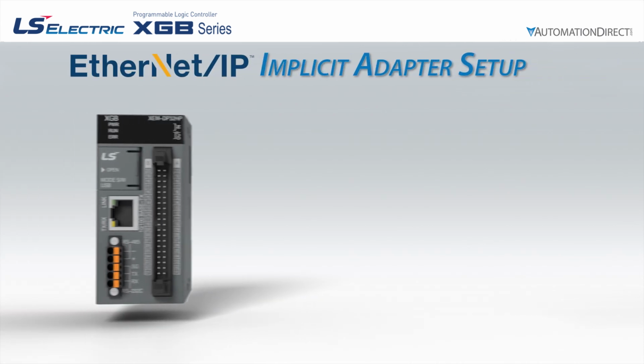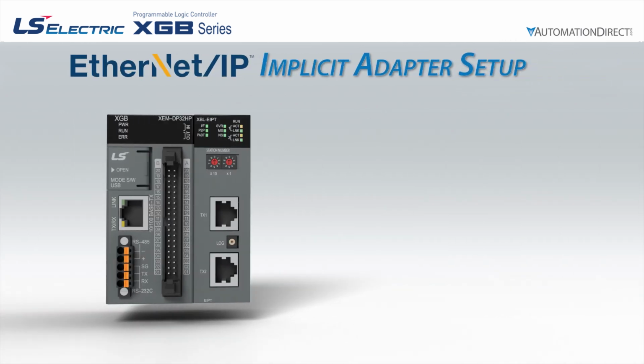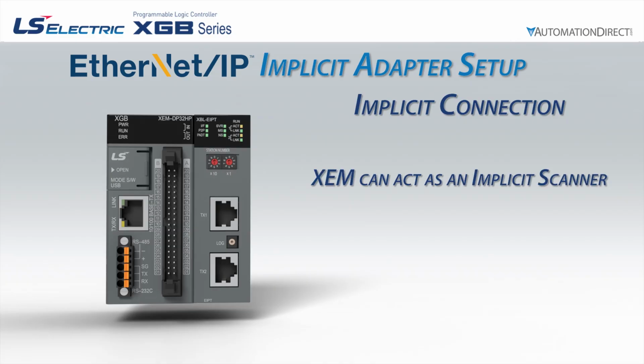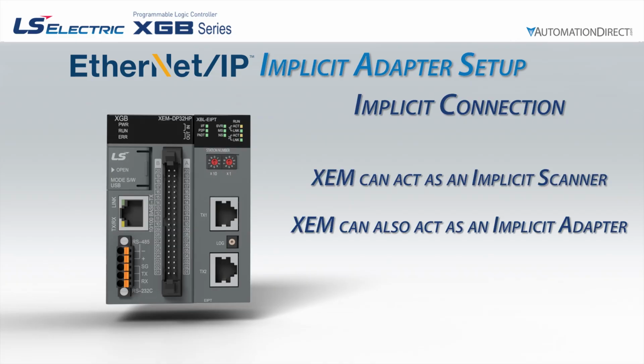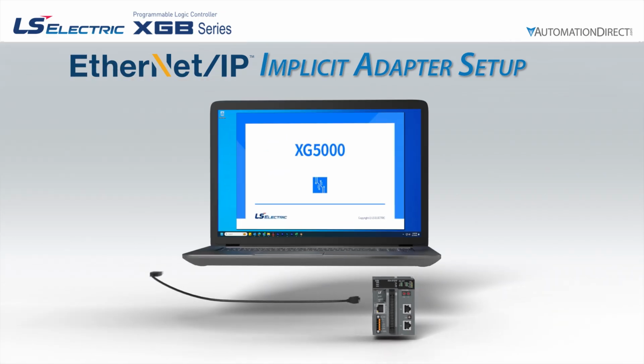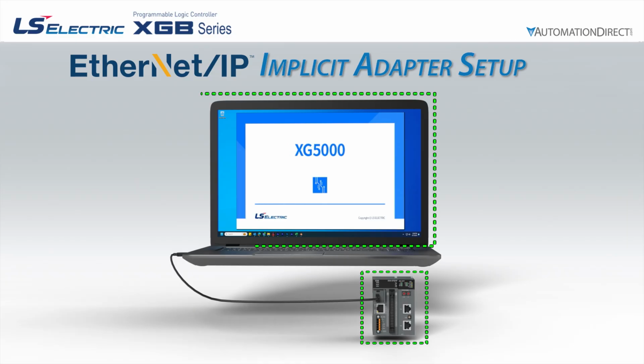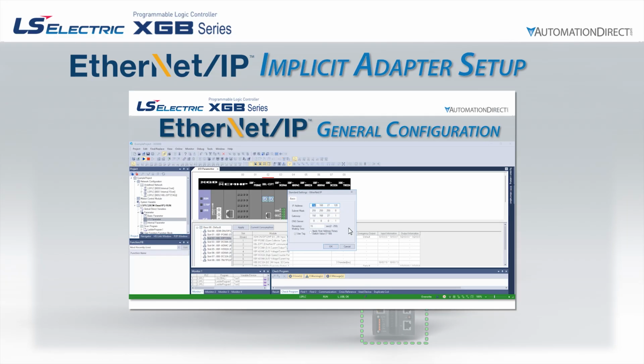If our XGB PLC has an EIPT module installed, we can set up an implicit Ethernet IP connection. The EIPT module is capable of being an implicit scanner that initiates a connection, or an implicit adapter that is available to be connected to. To set up the PLC as an implicit adapter, we first must configure the EIPT module and the peer-to-peer connection. These are both covered in a separate video.